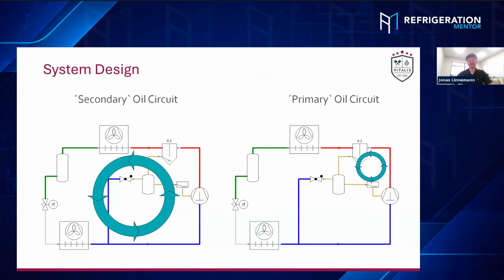Yeah, 100%. And in the primary oil circuit, you can handle the oil. You just refill as needed to the compressor. You have it stored in the oil reservoir. As soon as it travels out of the system, you can't really control it anymore. You need to rely on the oil return in the suction lines. It's just a good guess, hoping not to get any liquid or oil slugs coming back to the compressor. So that's not very easy to handle.